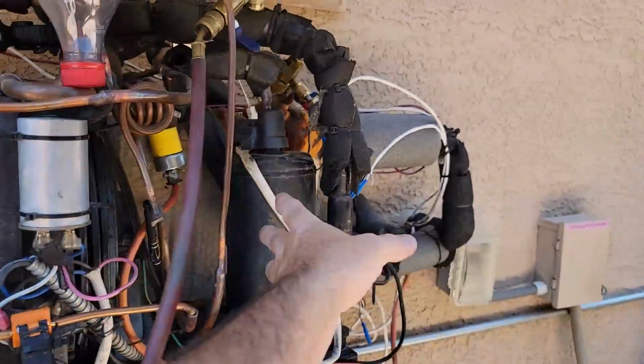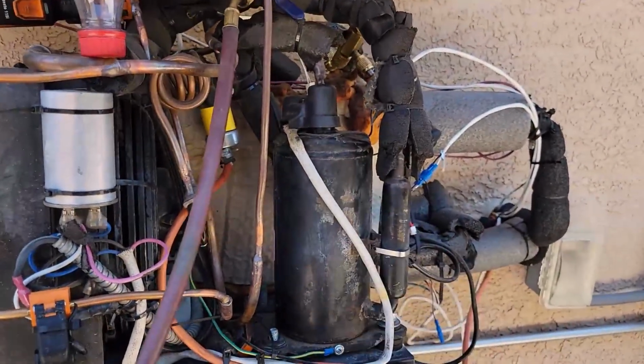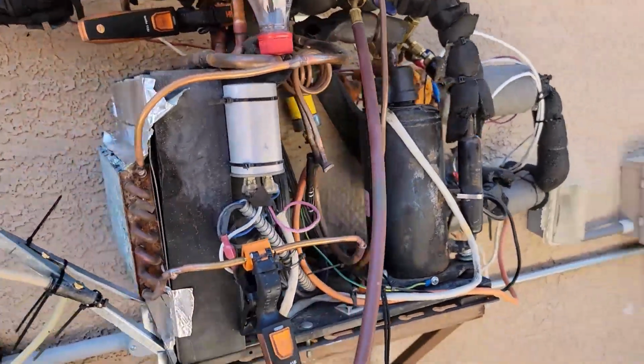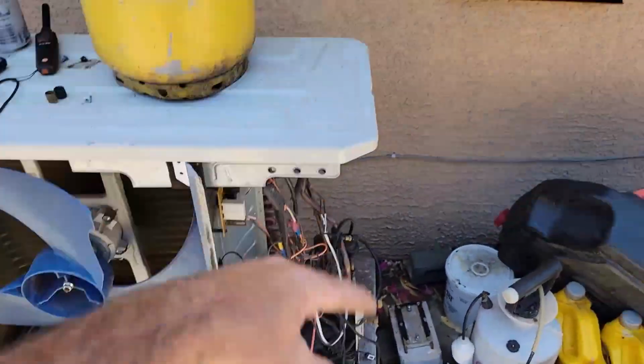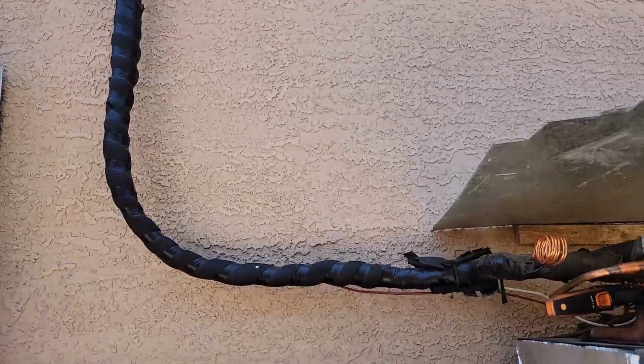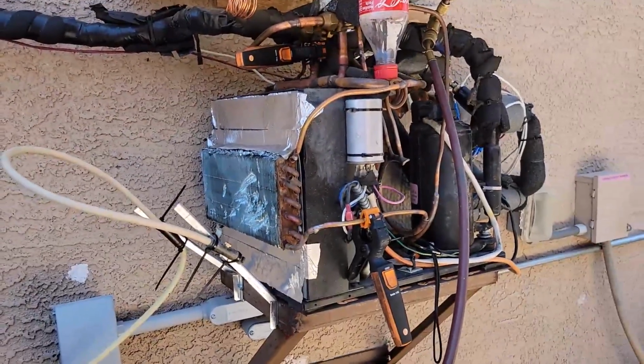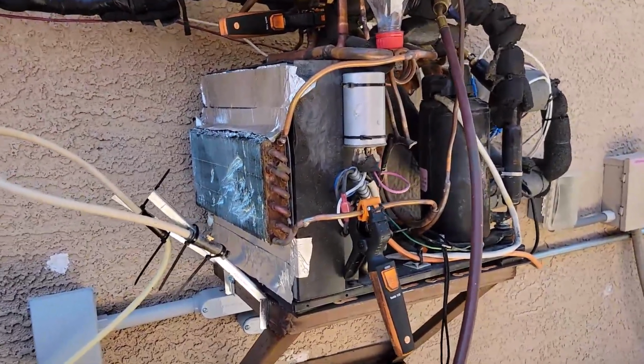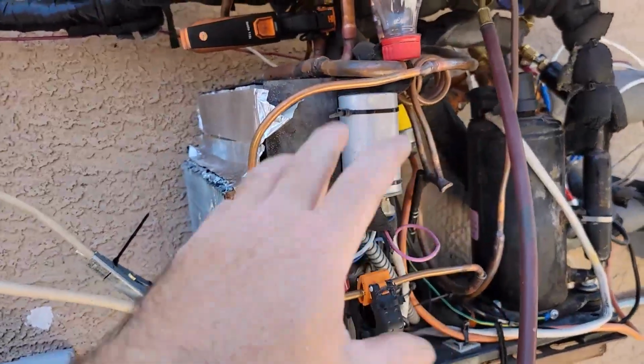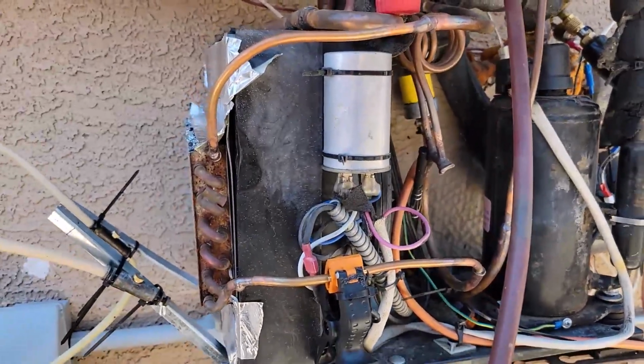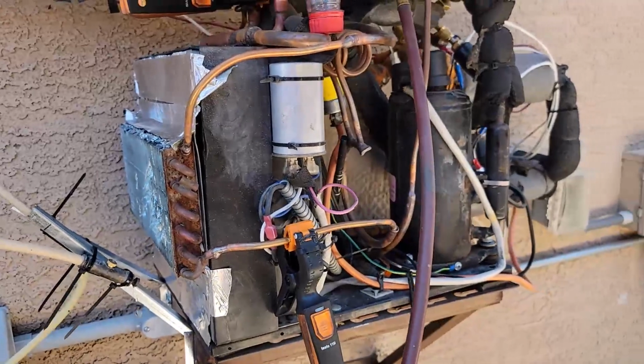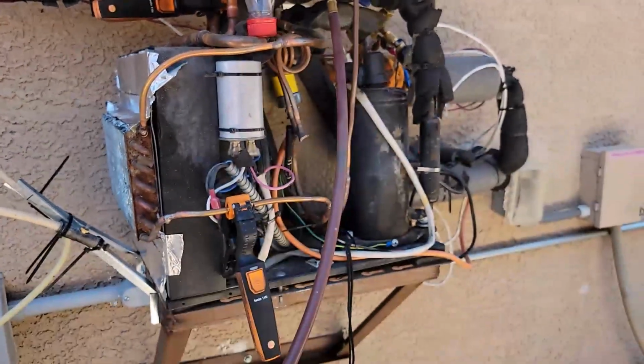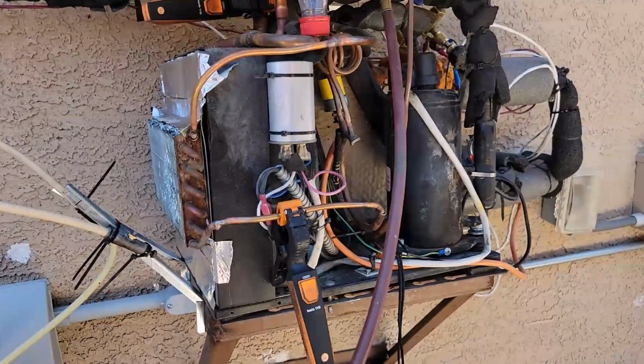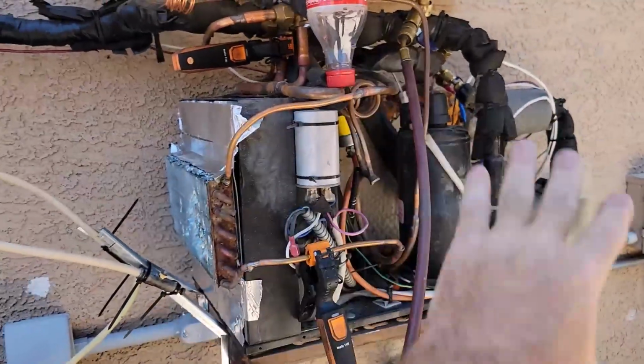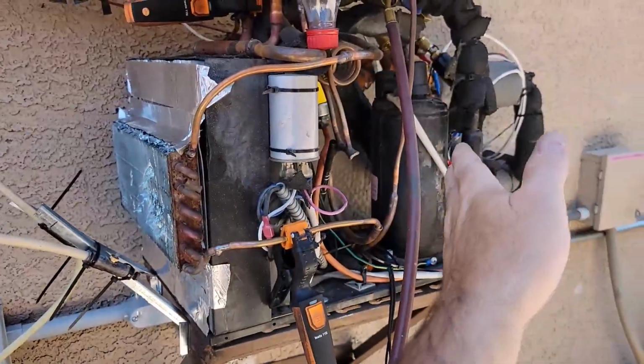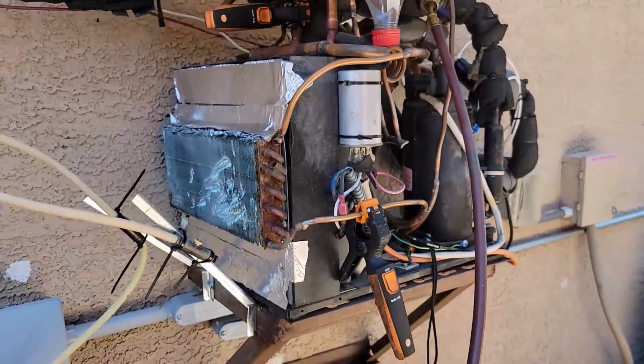The reason I had to keep this small is because I noticed, with a little tiny compressor like this, not even a 1-ton compressor, it's like 3/4 ton or something, when I tried to tie it into this last year, it air conditioned the snot out of that room, but it wasn't efficient at putting the heat into the water heater. So I had to keep the volume limited for it to be efficient at heating the water. After I put this back in here, it was back to efficiently heating the water, just like before, when this was strictly an outdoor coil and heat exchanger for the water heater heat pump.